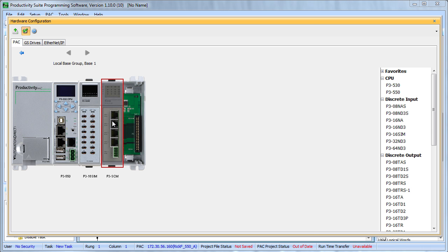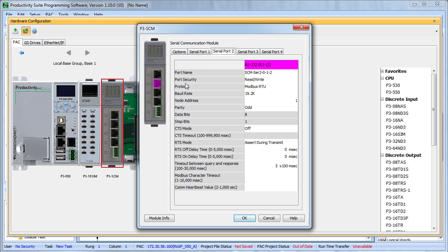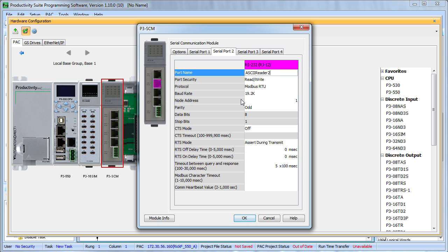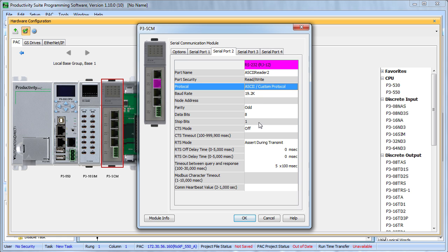Step 2 – Double click on the SCM to configure its ports. We'll use port 2 in this demo. Let's give it a name we understand. We are going to be reading some ASCII characters in this demo so let's call this ASCII Reader Port 2. Normally I would leave the protocol at Modbus, but for our demo we are going to be reading ASCII characters so we'll use the ASCII protocol so we can test it with a simple terminal program.